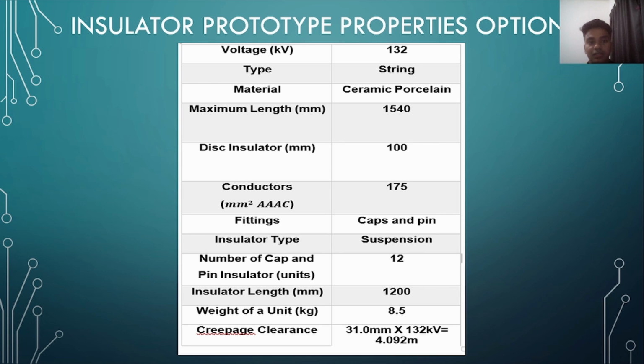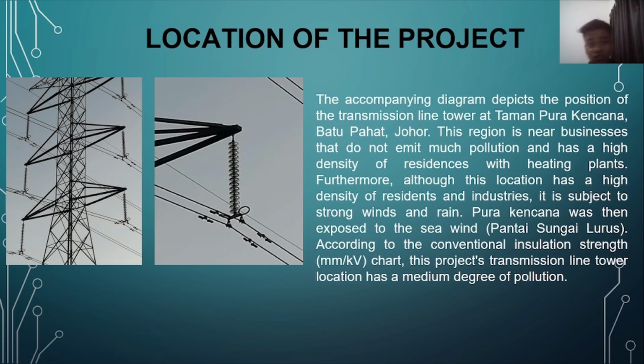Okay, next, this is the insulator prototype property option for our project. The voltage that we have chosen is 132 kV. The type of insulator is string. The material is ceramic porcelain. The maximum length for the 12 insulators is 1540 millimeter. For this insulator it is 100 millimeter. For the conductor it is 175. The cap and pin insulator type is suspension. The number of cap and pin insulators is 12. Insulator length is 1200 millimeter. Weight of a unit is 8.5 kilogram. Lastly, its creepage clearance is 4.092 meter.